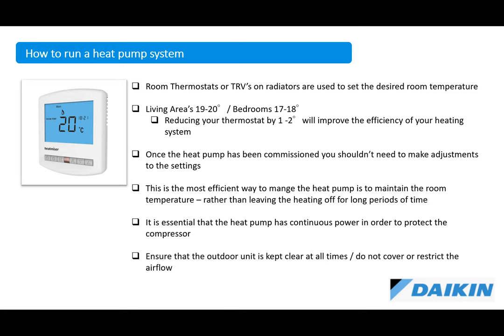So the most efficient way then to manage your room temperature is to set your room stat or your TRVs to, say, for your living spaces, 19 or 20 degrees and allow the heat pump to maintain that temperature. It is a kind of foreign concept to anybody who's used to running an oil boiler, because the norm would be to turn it on and turn it off as quick as you can so that you don't use too much oil. But with heat pumps, actually, you want the heat pump to run and not to be doing really hard work all the time. And to do that, you maintain the temperature.